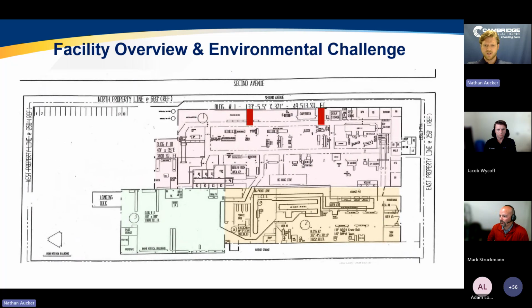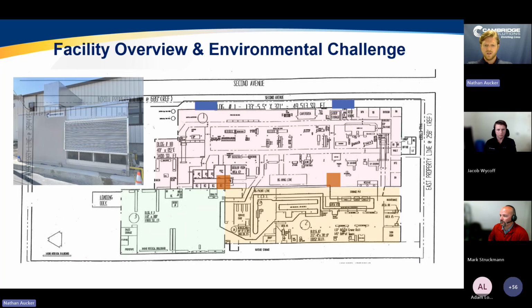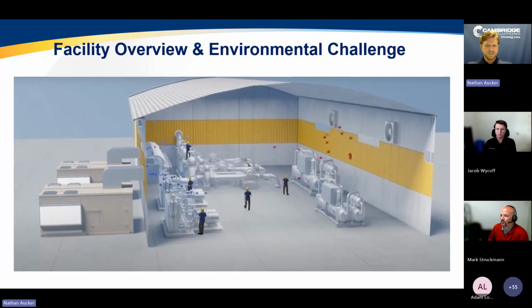These are our heating units originally, and we decided to jump forward and use 2-stage evaporative product here. So those are shown here in the blue, and those are really effective in these spaces. Depending on the humidity of the space, you can either cycle from indirect, which would be sensible cooling, or adding even a 2-stage direct to the facility. And what we found was, and the orange here, the exhaust, what we found was in this facility, we would hold around 77 degrees when outside temperatures were low to mid 90s.